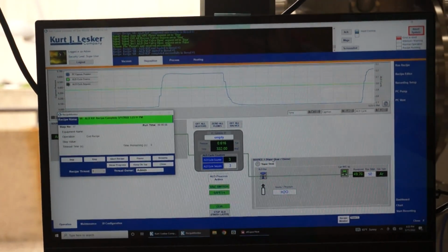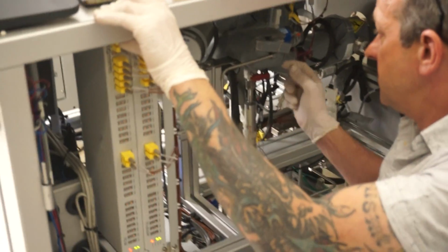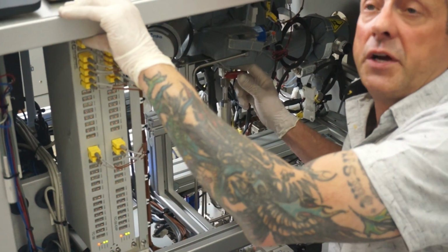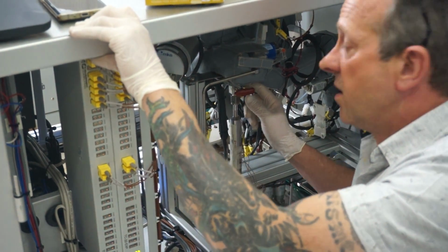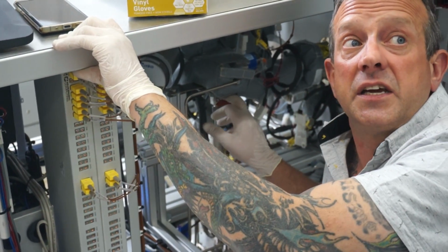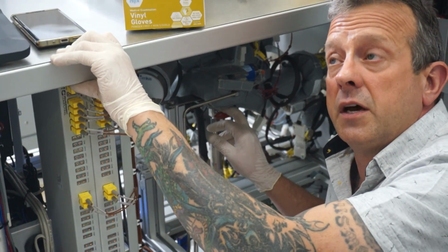So I pump purged, I got rid of the atmosphere that was between this valve in the coupler and the coupling of the 3/4 inch VCR fitting. So you didn't open the valve yet? I didn't open the valve yet, but I want to make sure that's not leaking. I want to have some degree of confidence. It ain't going to be 100%.